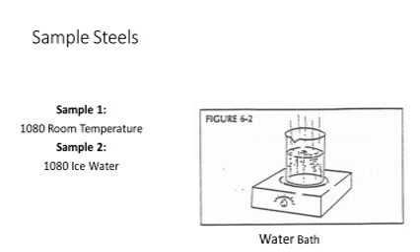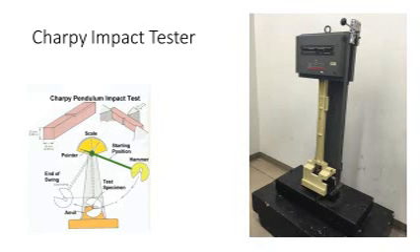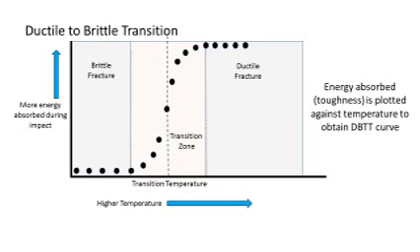The samples were held at warm temperatures and also placed in ice baths. At the bottom of the Charpy tester, the swinging arm strikes the sample. As the sample is hit, the energy dissipated — from the swinging arm's original potential energy to kinetic energy — is the impact energy of the sample, measured in foot-pounds. The collection of sample impact energies at each temperature gives the data needed to plot the ductile to brittle transition temperature range.